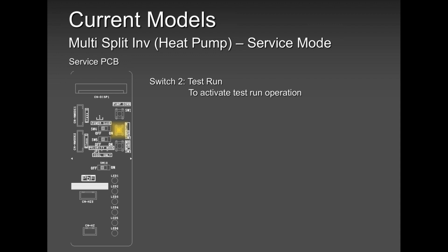That's why I tell my guys, when you're done, turn on one unit at a time. Leave test run for when you have a problem. When you have a problem 6, 7, 8, 9, 10 years down the road, put the unit in test run, let the compressor run like crazy to the maximum. You will have the opportunity to measure your running amps, your pressures, and you name it. So please, leave test run for service issues. When you have service problems, you can use that test run.